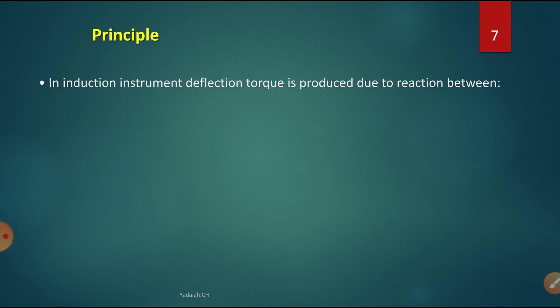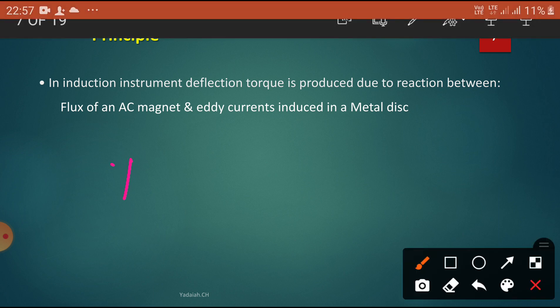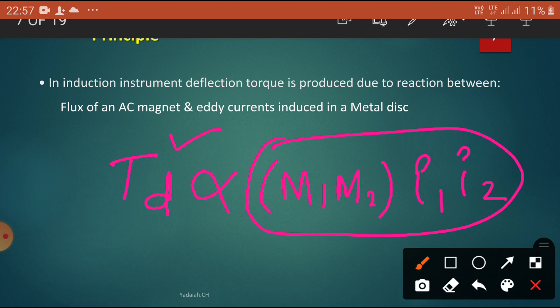Now let us see the basic principle of the energy meter. In the induction instrument, the deflecting torque is produced due to the reaction between the flux of an AC magnet and eddy currents induced in a metal disc. The deflecting torque required to rotate the disc is directly proportional to the interaction of M1 and M2, which produce currents I1 and I2 in the aluminum disc. These instruments are used only for AC purposes because induction means AC.